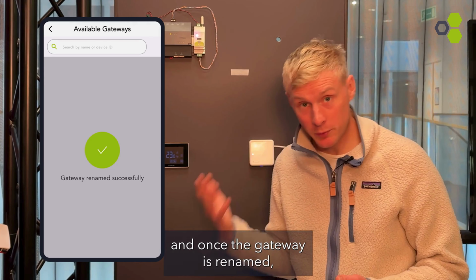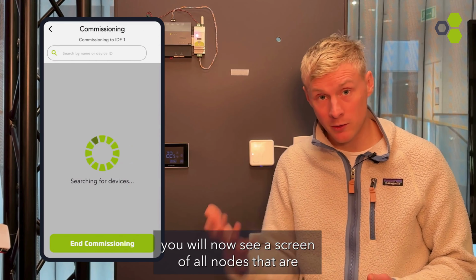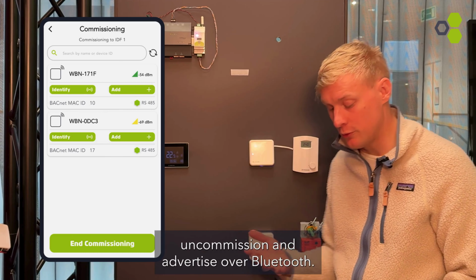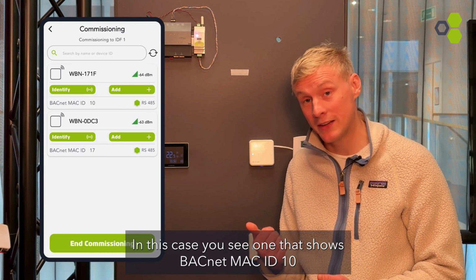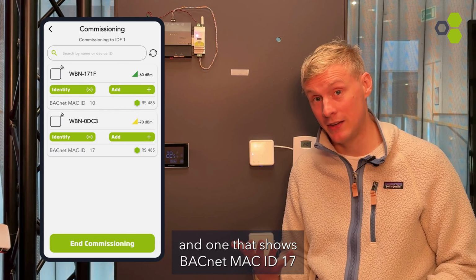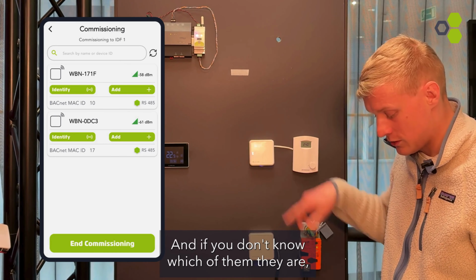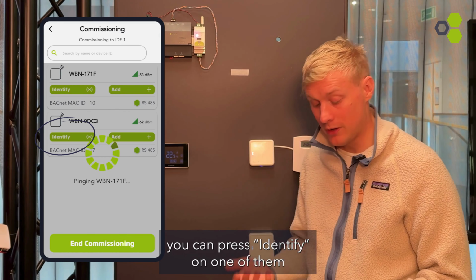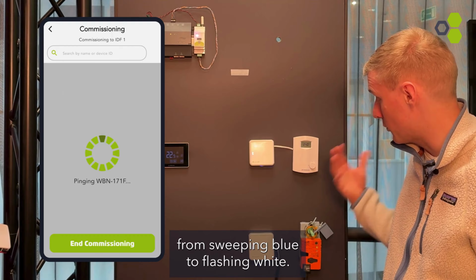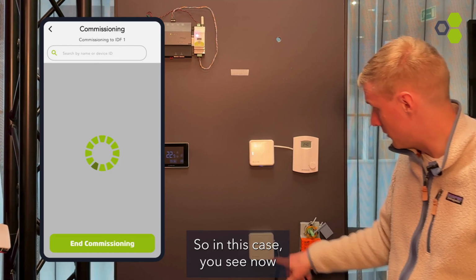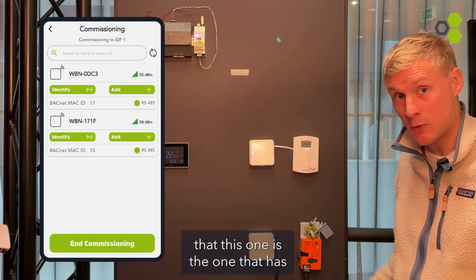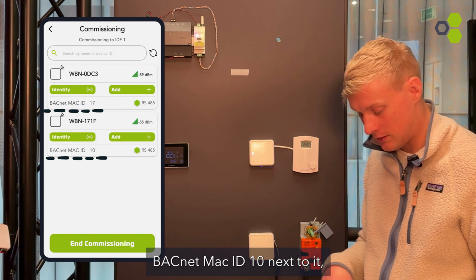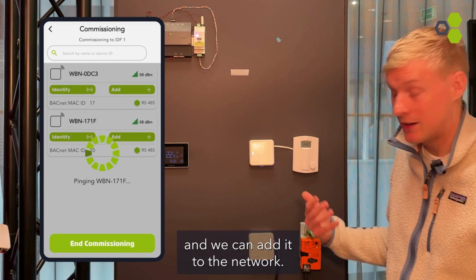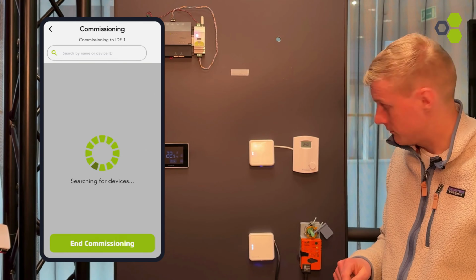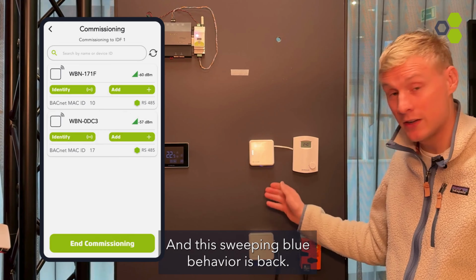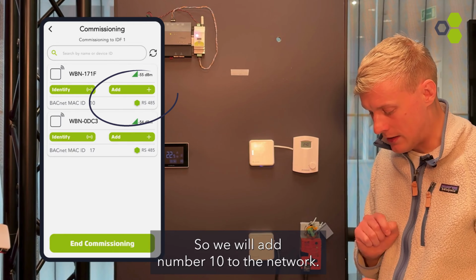And once the gateway is renamed, you will now see a screen of all nodes that are uncommissioned and advertised over Bluetooth. In this case, you see one that shows BACnet MAC ID 10 and one that shows BACnet MAC ID 17. And if you don't know which of them is which, you can press identify on one of them, and then that one will change from sweeping blue to flashing white. So in this case, you see now that this one is the one that has BACnet MAC ID number 10 next to it. We can now turn off the identify and we can add it to the network. And now you see that the pinging is off and the sweeping blue behavior is back. So we will add number 10 to the network.